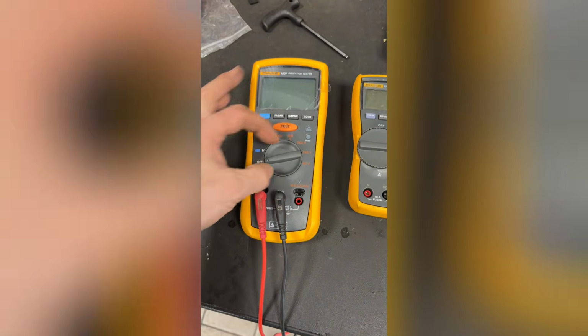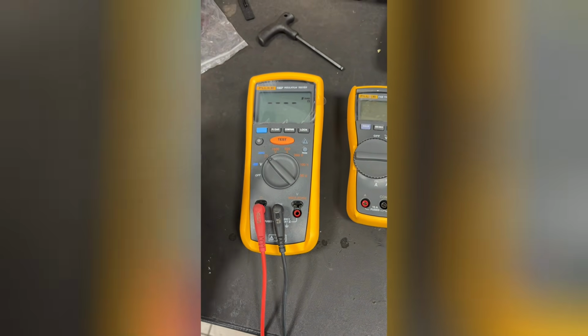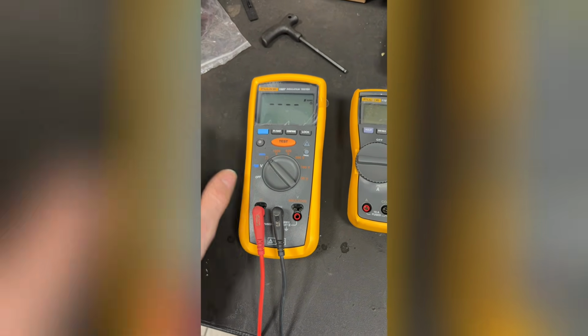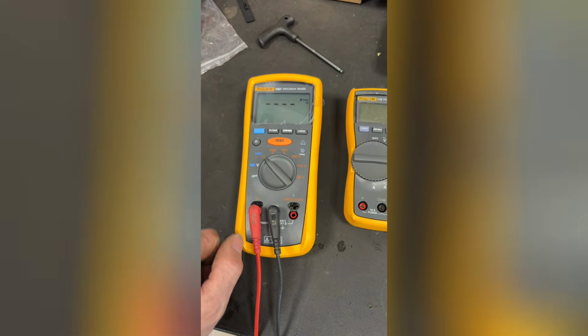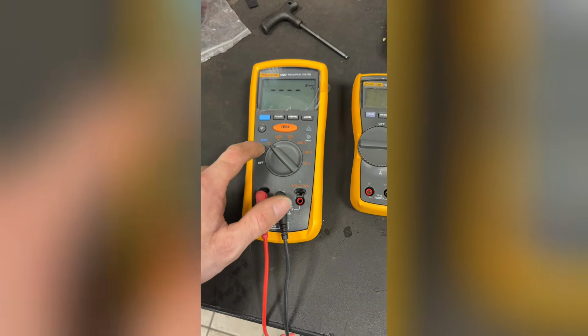So what I'm going to do now is go to this. I'm not going to zero it, but in reality you would. What we're doing is not an insulation test, but an isolation test - the resistance measurement. It's just an ohmmeter, isn't it?